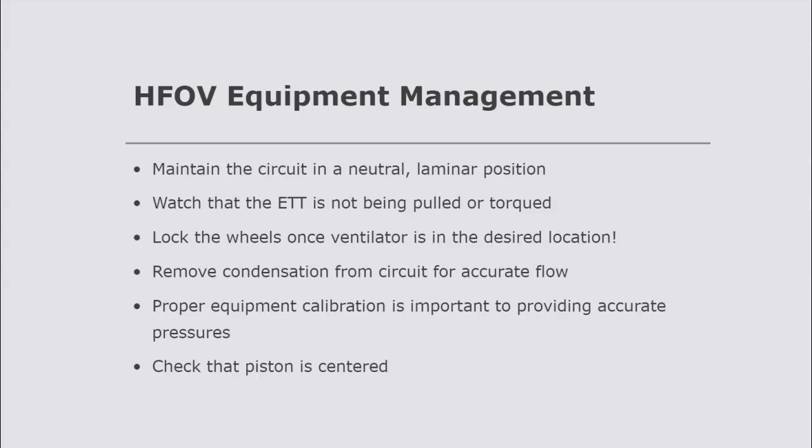The other thing is to check the piston is centered. The easiest way I like to do it is, I'll show you where the start-stop button is. I like to just pause my oscillation, press my start-stop button, and then that is the easiest way to make sure your piston is centered, because then the oscillation isn't holding and you can see where your piston is located. I will show that to you.